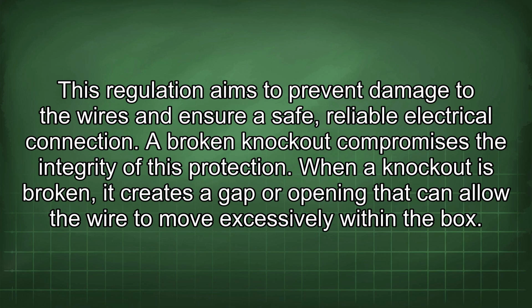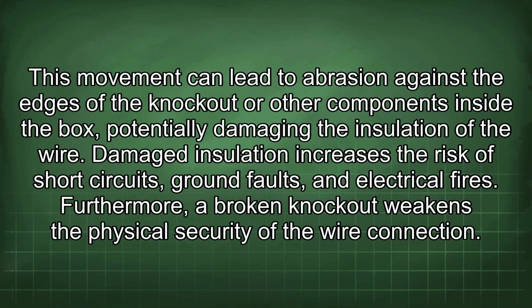When a knockout is broken, it creates a gap or opening that can allow the wire to move excessively within the box. This movement can lead to abrasion against the edges of the knockout or other components inside the box, potentially damaging the insulation of the wire. Damaged insulation increases the risk of short circuits, ground faults, and electrical fires.